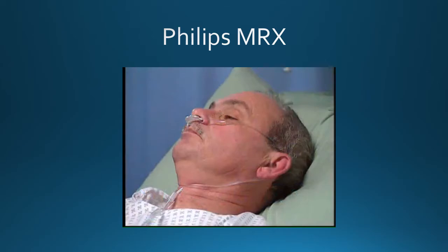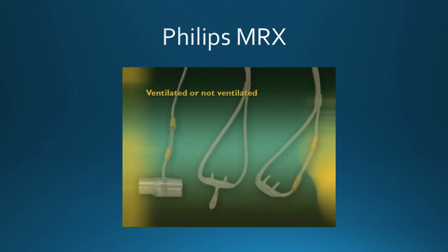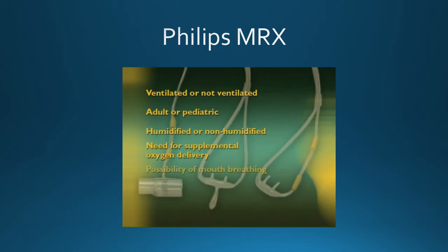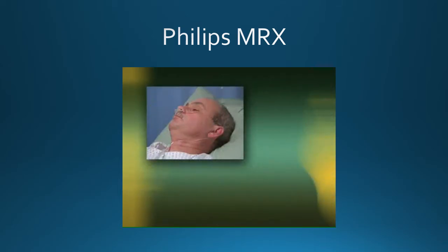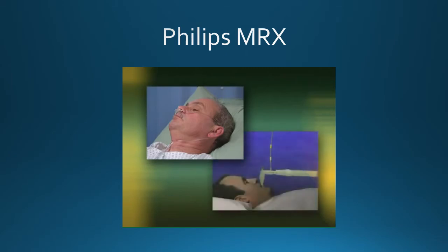The first step in setting up the microstream system is to select the appropriate filter line. There are 5 factors to consider when selecting the filter line. Patient situation, ventilated or not ventilated. Patient type, adult or pediatric. Ventilation type, humidified or non-humidified. The need for supplemental oxygen delivery. And the likelihood that the patient will switch between oral and nasal breathing. There are 2 filter line options in microstream monitoring, non-intubated nasal cannula and a filter line with an airway adapter.